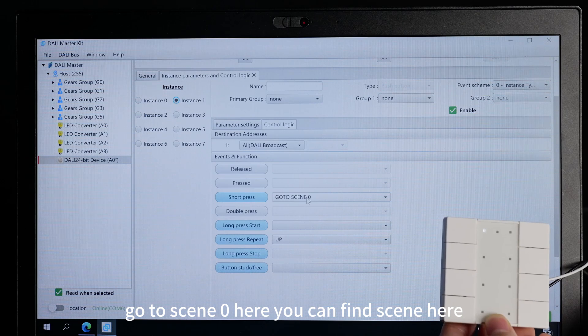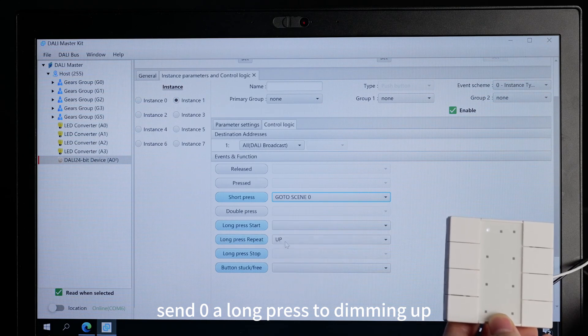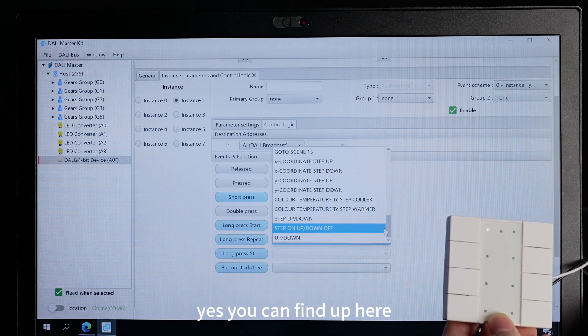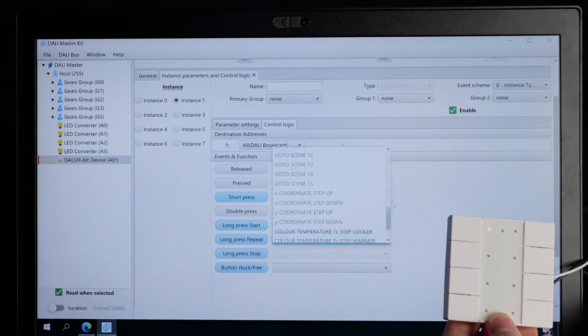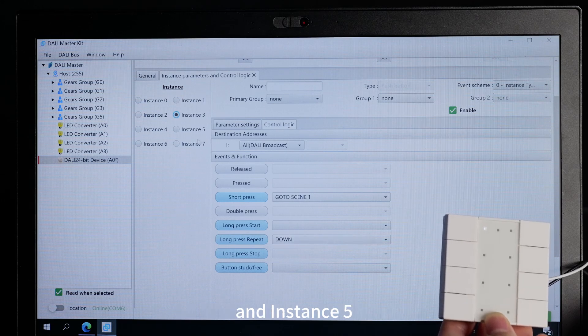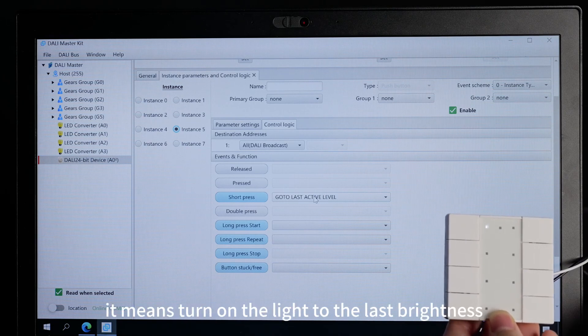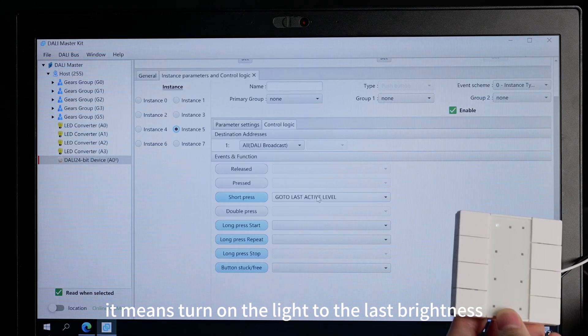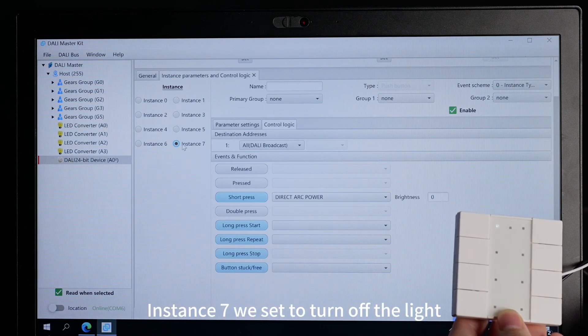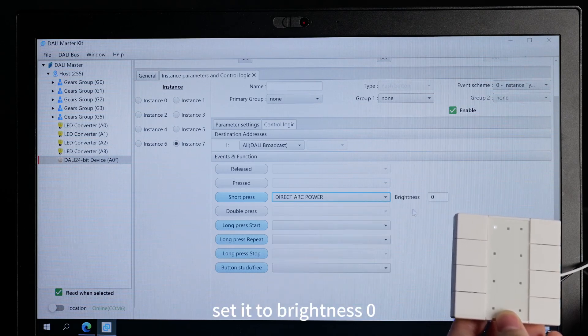Short press to go to scene 0 — you can find scene here. And long press to dimming up. Dimming up. And instance 3, we set it to go to scene 1, and long press to dimming down. And instance 5 — go to last active level, which means turn on the light to the last brightness. And instance 7 — we set it to turn off the light. You can also set it to brightness 0.